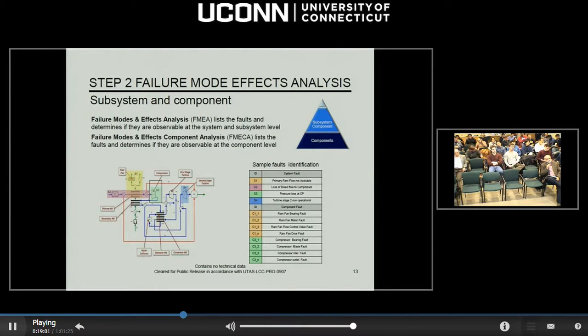So remember, we talked about going down, we do the analysis going down. But once we're at the bottom, because we've got more clarity about how the system works, we start moving back up, looking at it going back up. This process is not a one-time deal, it's never ending. Every design cycle goes through multiple iterations where we're constantly updating the fault trees, the hazard assessments, the FMEAs, as certain things change.